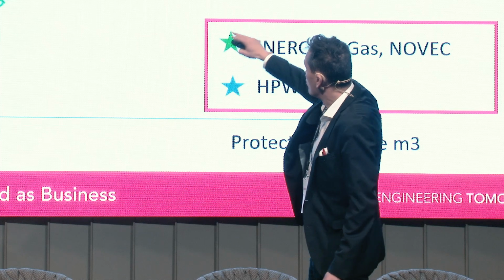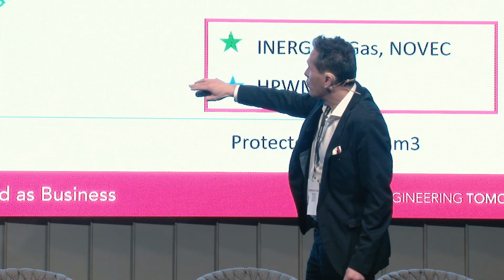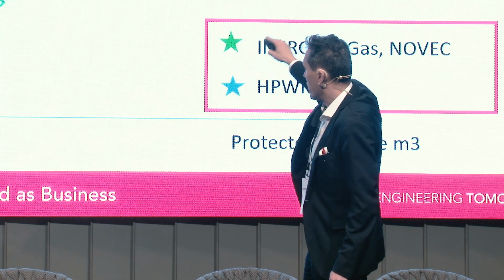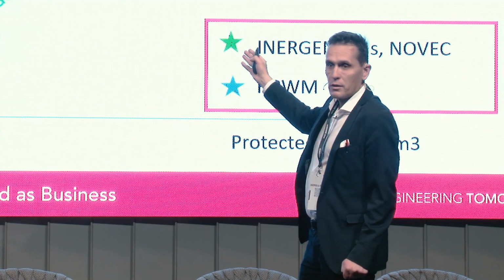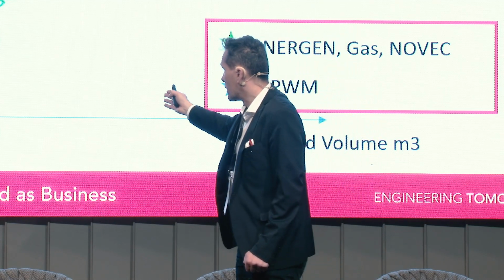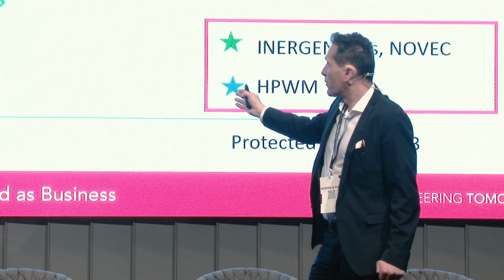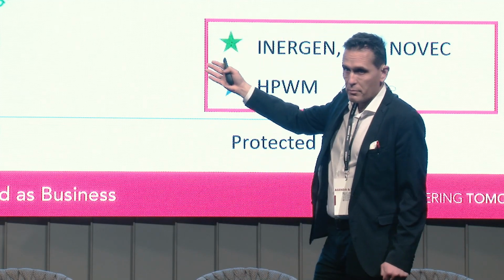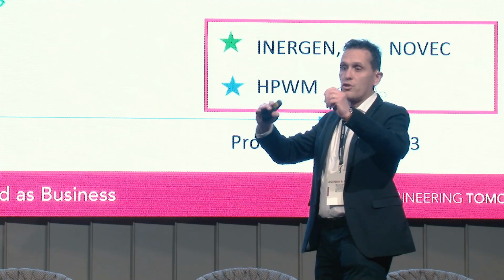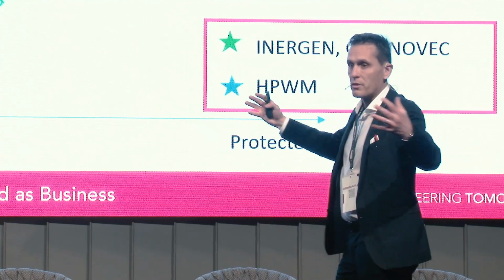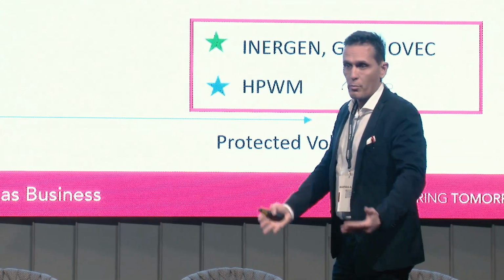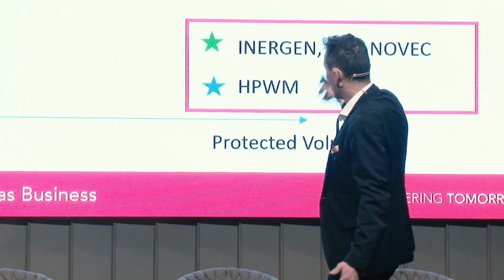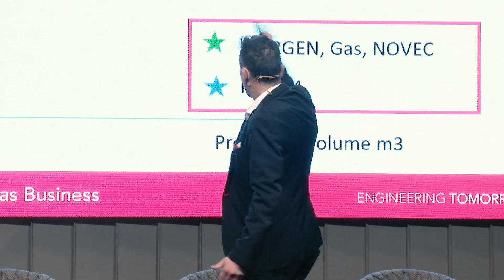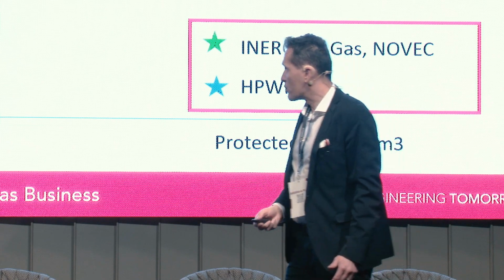If you did the square root calculation for high pressure water mist investment cost, the turning point is at 2,000 cubic meters, because you have to buy the pump unit, but after that, if it's bigger, you just add more nozzles. So the bigger the data hall, the cheaper we are compared to gas. I'm sorry, I left out the cost characteristics of high pressure water mist in this presentation.